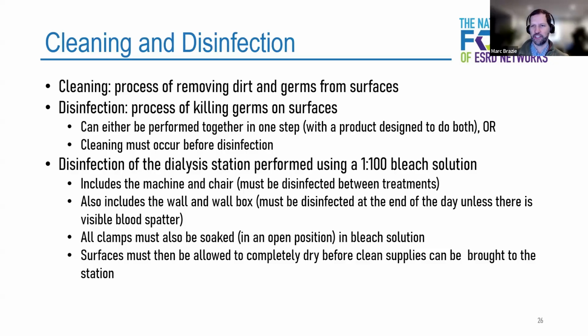Disinfection of the dialysis stations is typically performed with a bleach solution. It's usually a 1 to 100 diluted bleach solution. And this includes the entire dialysis station. So it's not just the dialysis machine itself. The chair also has to be disinfected. And both the dialysis machine and the chair have to be disinfected between every treatment. So if you're running 3 shifts in a day, you have to disinfect between your first shift and your second shift, and disinfect again between your second shift and your third shift.